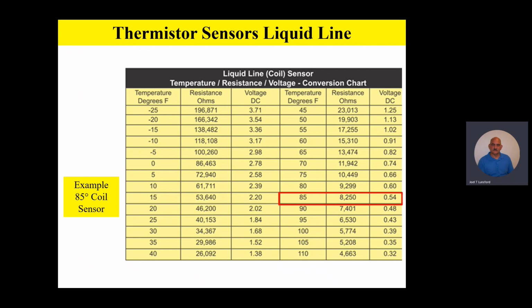Now remember, team, as long as the control board is able to support the sensors and you're reading the ohms on the sensor and if the DC voltage is very, very close, then you know the board is supporting that sensor. Anytime you take that sensor off the board, if you ohm it out at any given temperature, if it doesn't line up with this resistance or this ohm column on the sensor charts, then you know you have a bad sensor. And please remember, if you're having problems with your sensors, it's probably not the control board, it's probably the sensor that's bad. And again, the sensors, if they're open electrically, your meter will read OL. If it's shorted electrically, it'll be a very low ohm value, maybe 10, 15, maybe even 100 ohms. And if it's supposed to be, in our example there, 8,200 ohms, and it only reads, say, 100 or 150 ohms, then you know the sensor is partially shorted internally and it needs to be replaced.